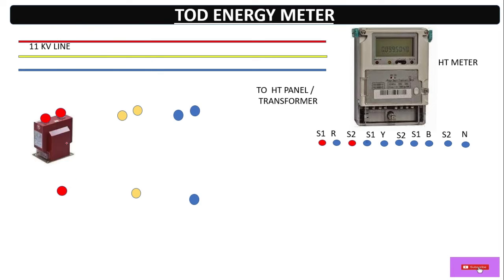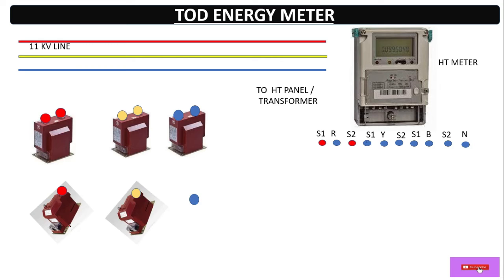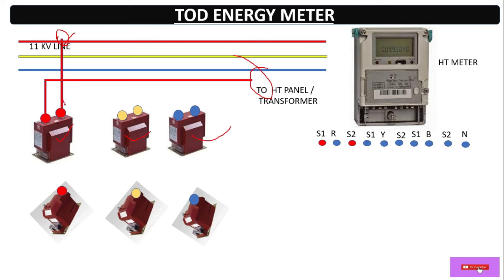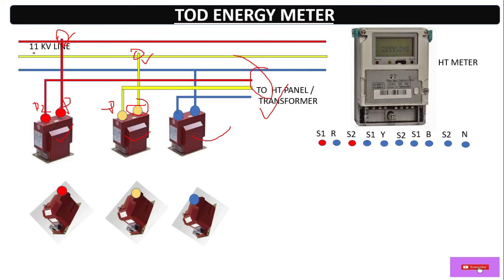To measure the energy consumption of this system, we take three CTs for three lines and three PTs for three lines. For the primary wiring, we tap the wire from the 11 kV line — for R phase, this is P1 and P2. Then from P2 it goes to the HT panel. Similarly, for Y phase we tap from the 11 kV point of supply — P1 in, P2 out, which goes to the HT panel or transformer. Similarly for B phase. This completes the primary connection wiring.